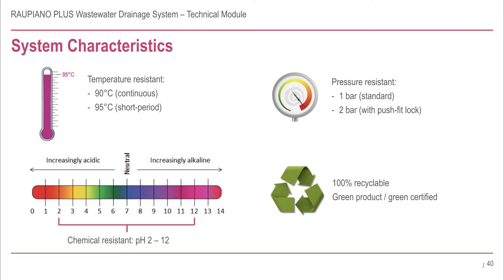Raupiano Plus is manufactured from mineral-reinforced polypropylene, carefully processed to produce excellent attributes suitable for drainage systems. It is temperature-resistant to a constant temperature of 90 degrees C and 95 degrees C for short durations, and chemically resistant from pH 2 to 12. The bare push-fit joints are pressure-resistant to 1 bar, increasing to 2 bar with the push-fit lock. Raupiano Plus is also fully recyclable and is a green product, suitable for use in Green Council certified buildings.